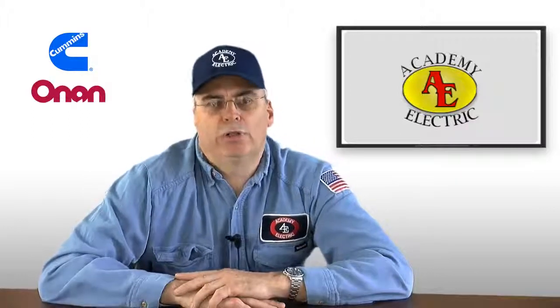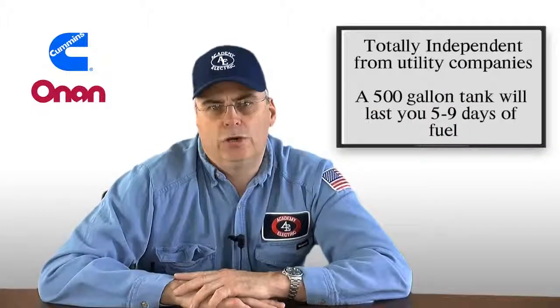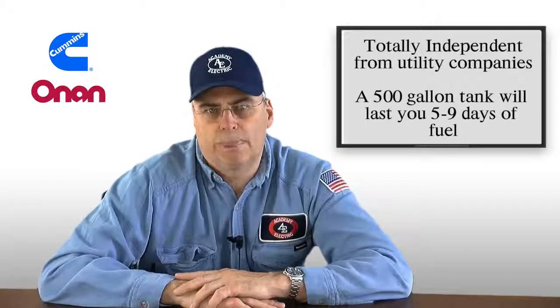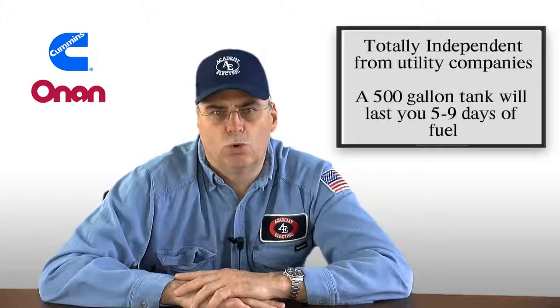What we've been doing for customers in the area is excavating a hole and burying a 500-gallon propane tank somewhere in your yard. The requirements are pretty simple and we've done this multiple times. By putting in a propane tank, you've now become totally independent — you're not relying on a utility company for your fuel source. A 500-gallon propane tank will give you somewhere between five to nine days of fuel for a small spark-ignited engine, which is enough for you to get by during a power failure.